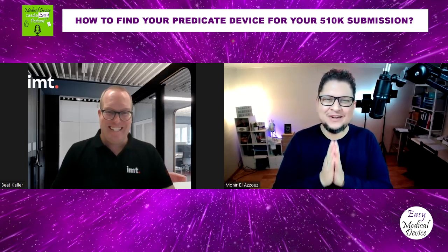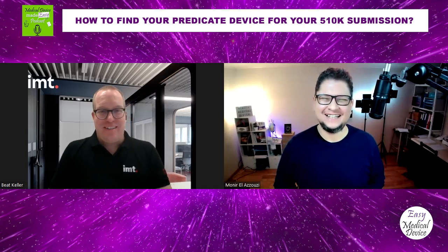Yeah. So if you have something new, then you need to go to PMA or the de novo path, which is different, where you have to show that it's clinically working, that it is safe, etc. But if there is a device on the market and the risk is not too high, so it's mainly a class 2 device, then you can show equivalence to go on the market. Yeah, and I'm also working on some 510Ks, and I know that a lot of people, when they are looking at 510Ks, hope there is a predicate device. I hope there is something on the market. Yeah, it's quite faster and not so expensive as a PMA or a de novo. Exactly. To be honest, true. The de novo fees are really high. I don't know really if there is a great justification for that, but yeah, it's really high in comparison to a 510K.